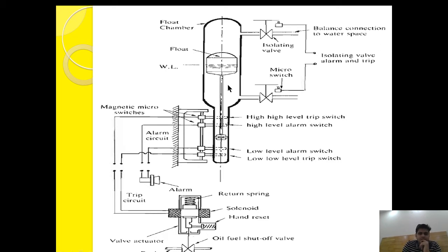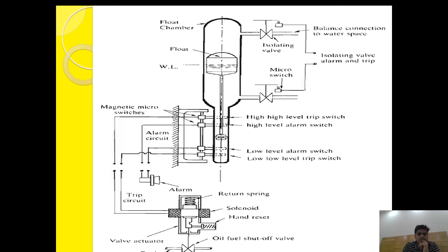The same logic applies when the water level is increasing. The float will move up, and when it reaches the high level alarm switch position, the alarm circuit will be activated through a micro switch, indicating a high water level alarm. If the situation is left unattended and the water level continues to rise, the float moves further up.